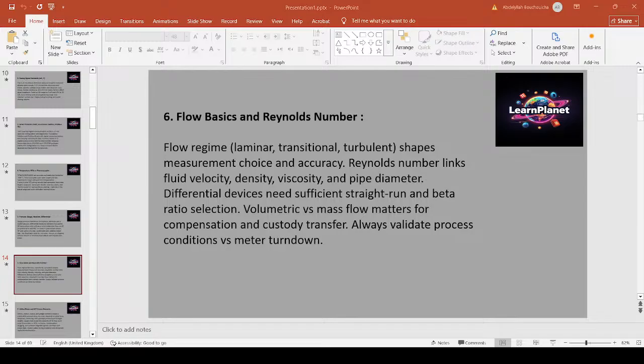Orifice, Venturi, a sufficient Reynolds number and the straight run maintain a predictable profile. Mass flow, Coriolis vs volumetric flow, magnetic or turbine matters for density compensation needs. Custody transfer often requires mass or compensated volumetric flow. Validate that the process run stays within meter turndown.